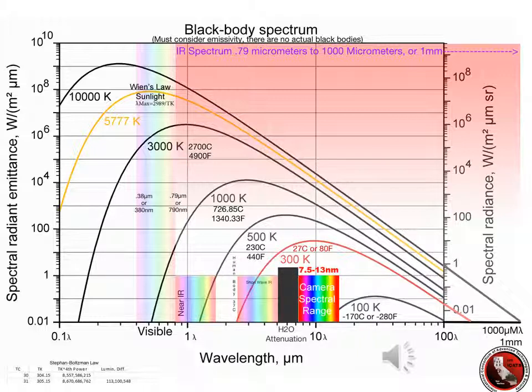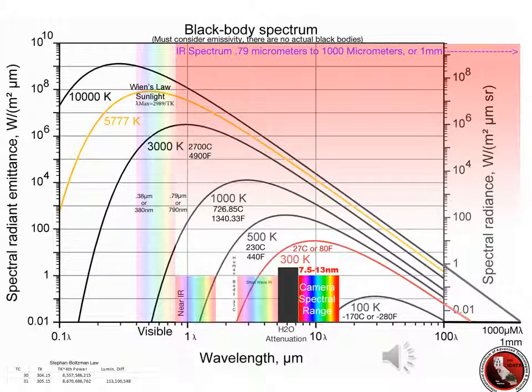The next spectrum to the left covers shortwave infrared cameras, which observe hotter objects. If you're inspecting boilers or other very hot objects, you need a shortwave or near-infrared camera — one capable of imaging objects that are close to or actually giving off visible light. Examples include light bulbs, smelting plants where molten metal glows with beautiful colors, or any high-temperature industrial process involving fire.